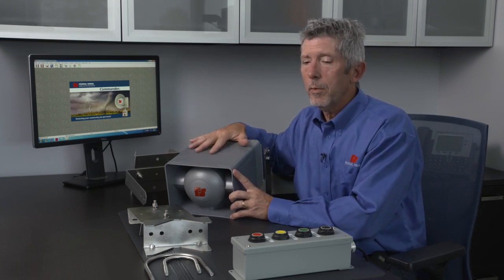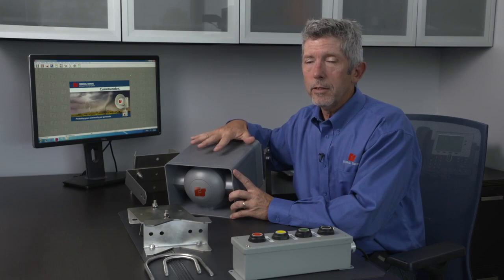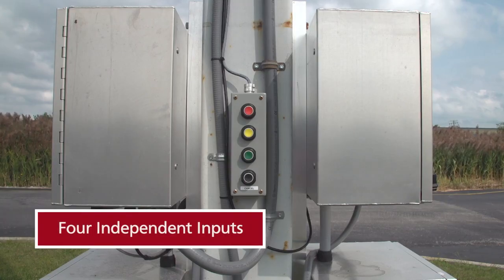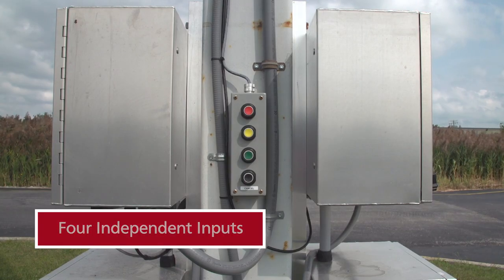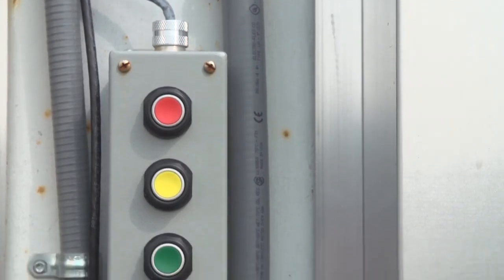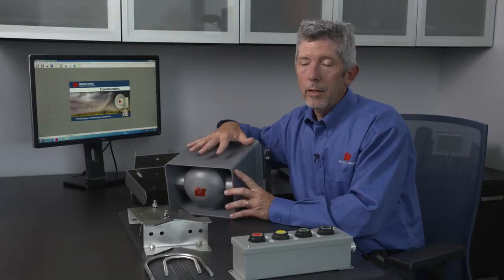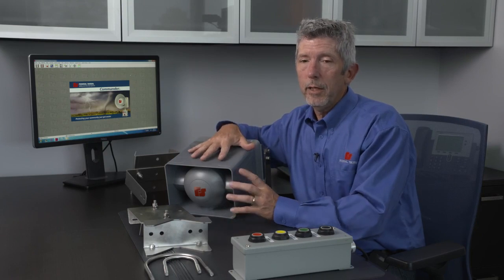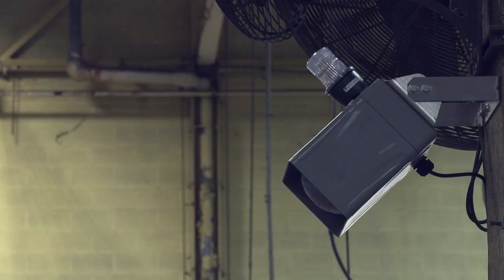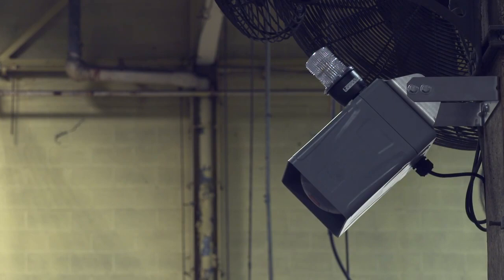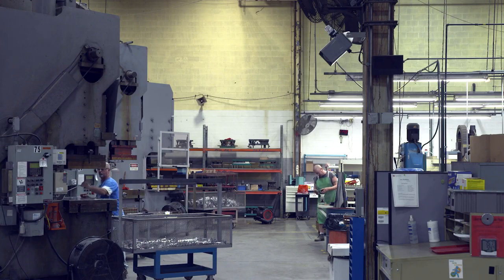What can I do in this standalone mode? Well, number one, it has four independent inputs. Those inputs can be wired for either being normally open or normally closed contact closures. You can then have each of those be either momentary or continuous. You can have it so that the relays are activated.